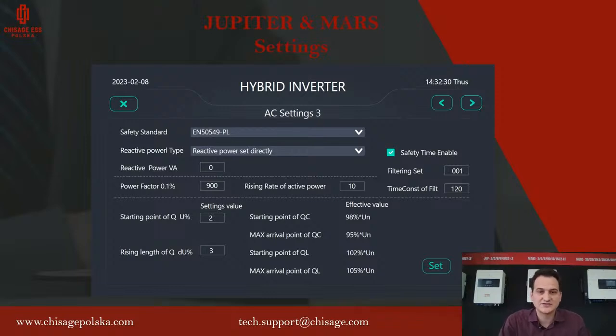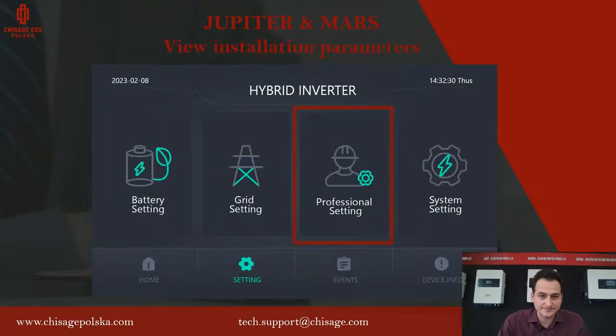All the other settings on this page are related to reactive power. We can set this reactive power in several ways. We can pick the way in reactive power type: reactive power set directly, or power factor, or we can use the Q curve to set this. So these settings we can fill in here.